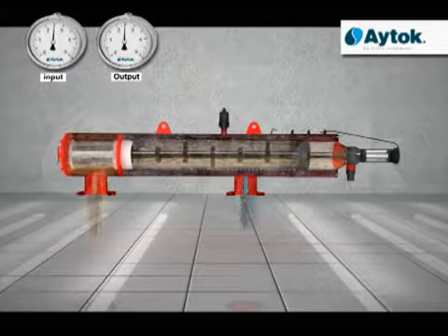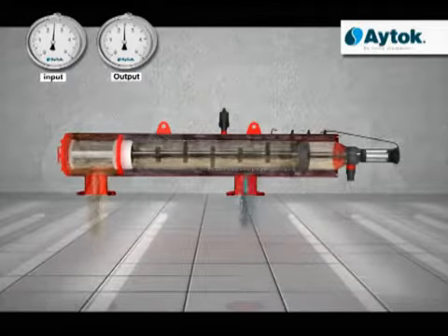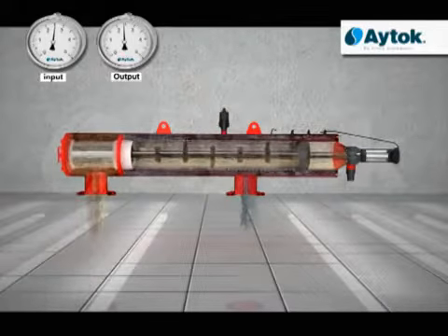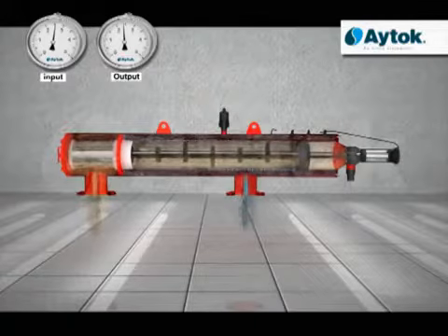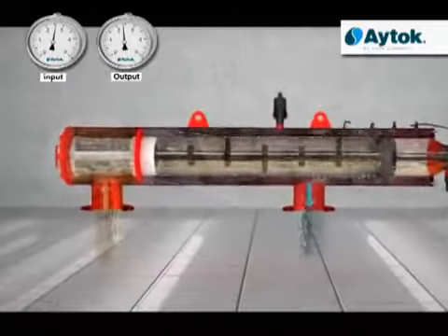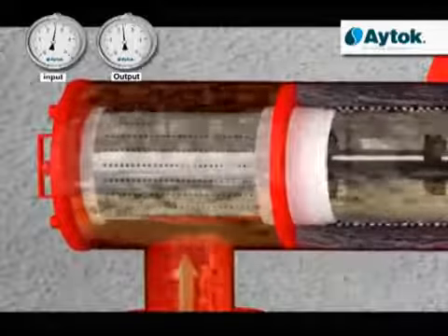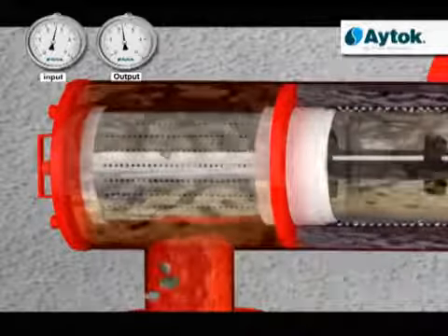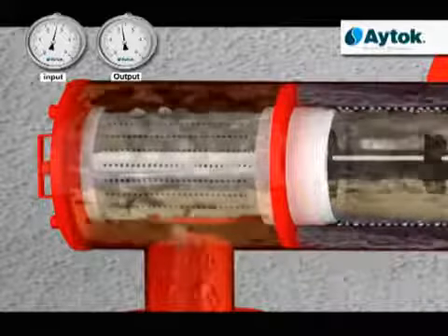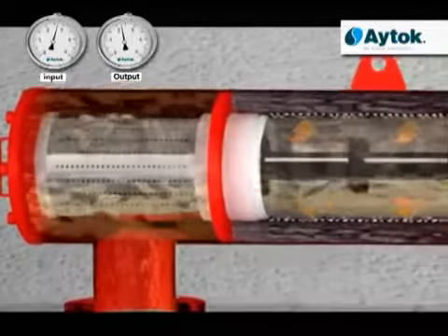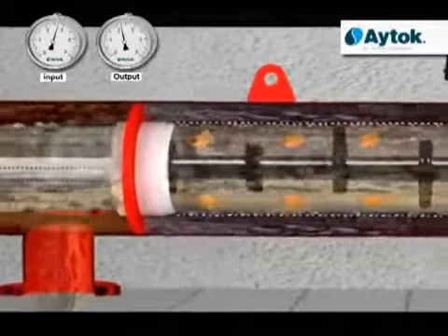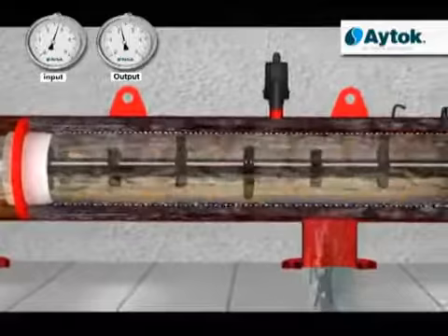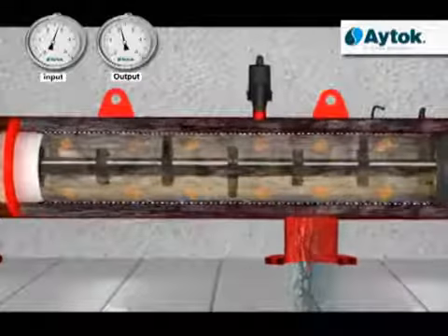HD filter explanation. The dirty water which comes from the entrance collector is subjected to pre-filtration in the coarse screen to prevent big particles inside it from damaging parts in the fine sieve's internal areas. After that, water goes to the second filtration part, where the fine sieve takes place, from the coarse screen.